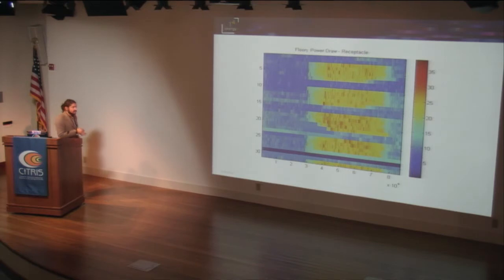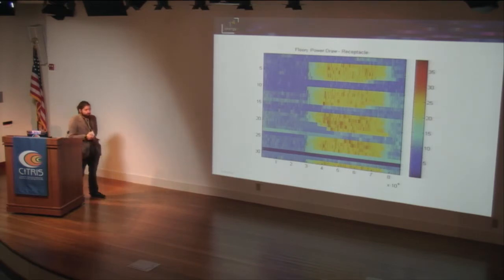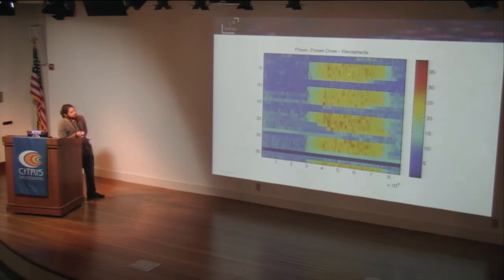Let's look at the second floor. And I know from auditing the second floor that this group here is users coming in and plugging in laptops. They're turning on LCD screens. But all these little spikes in the middle of the night are from the cafe. And I suspect that this large jump is from a computer lab on the floor.